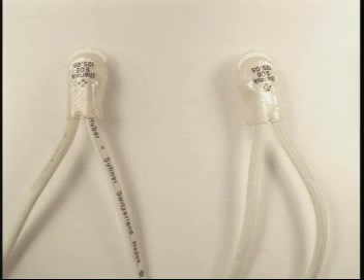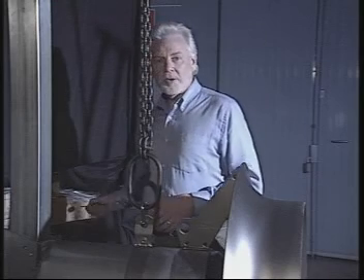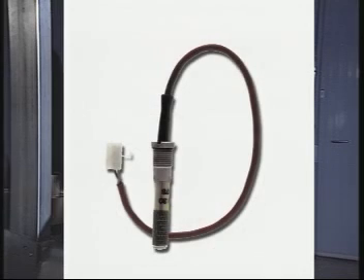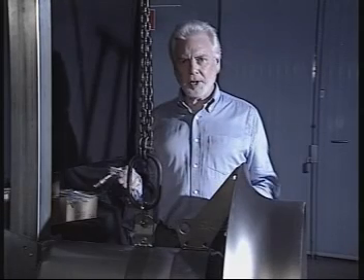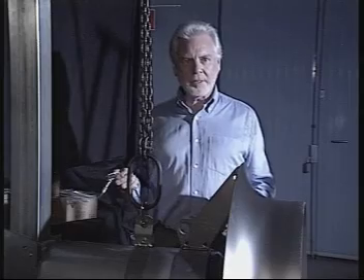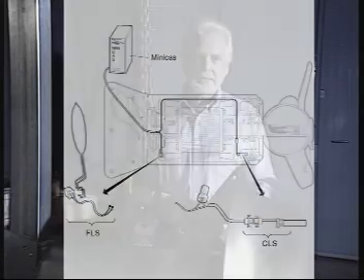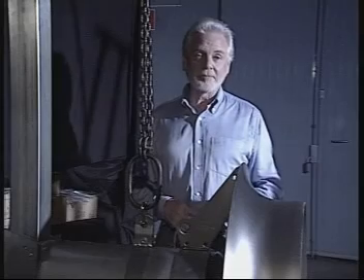Thermal switches, which control the stator's upper temperature limits, are a standard feature on all mixer stators, whereas FLS sensors for the detection of liquid in the stator housing and CLS sensors for water and oil detection are optional. Any combination of these sensors supplied with your mixer must be properly connected to a monitoring and control system to avoid damage and to make the warranty for the mixer valid.